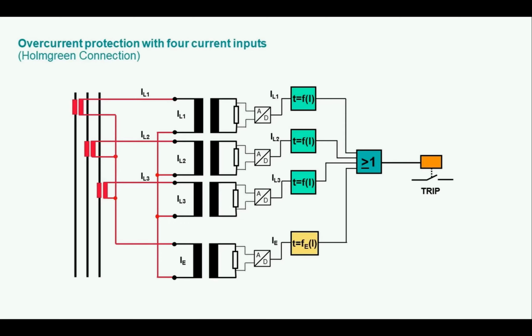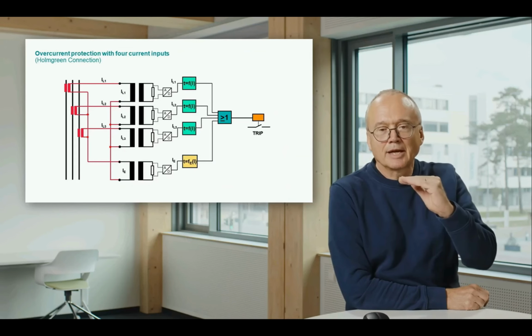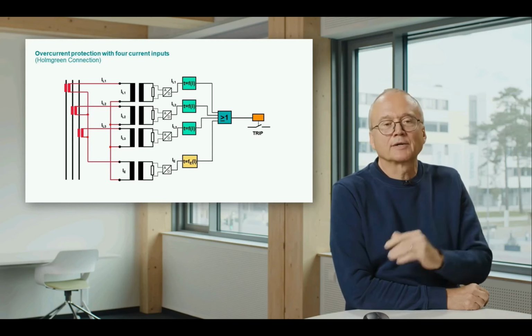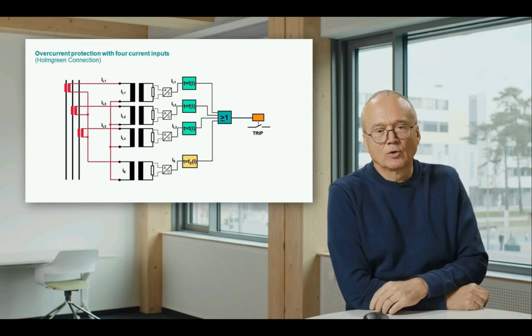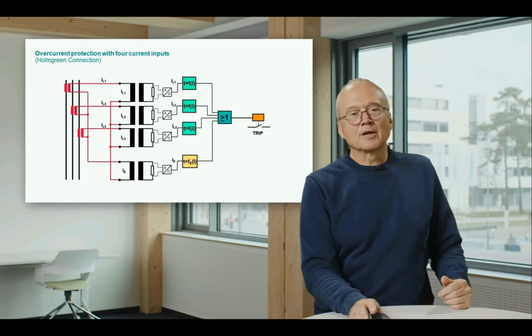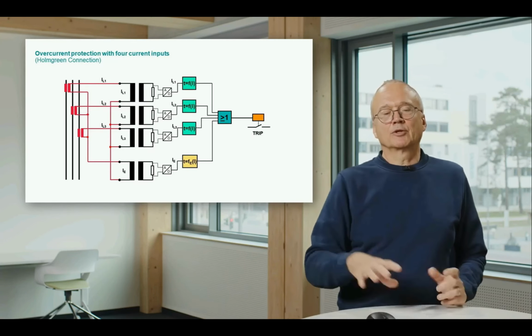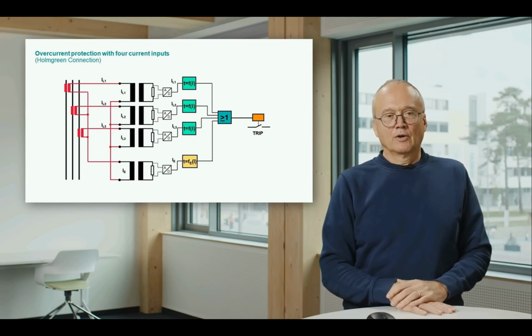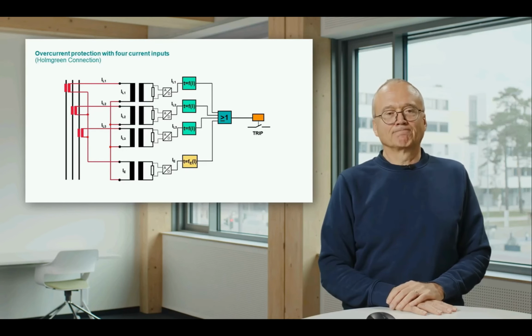We add a measuring input for the earth current, Holmgreen connection or internal computation, as I discussed, and then we add here this yellow block, and this yellow block has maybe the same timer settings, but it has a different current setting. It can have a significantly lower current setting to react on earth faults. That means this would be the total diagram of an overcurrent relay.